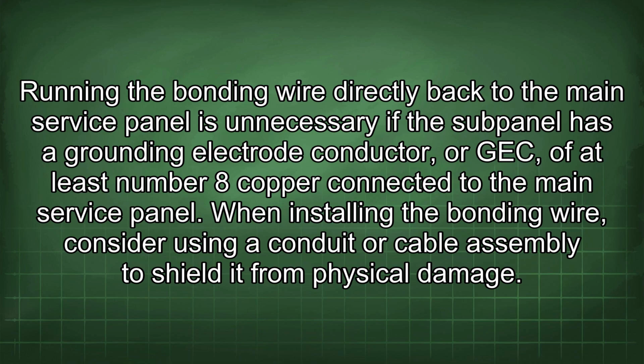Running the bonding wire directly back to the main service panel is unnecessary if the subpanel has a grounding electrode conductor, or GEC, of at least number 8 copper connected to the main service panel.